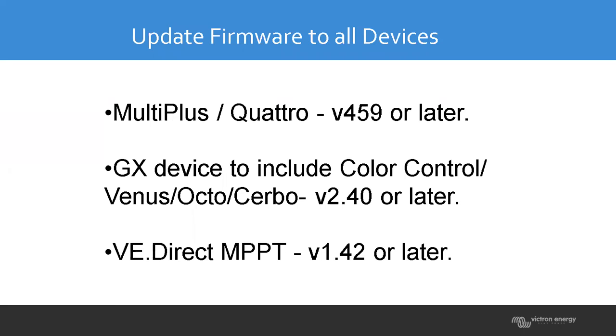We'll need to update the firmware to at least these firmware revisions. The Multi-Plus is 459 or later. The GX device, and that could be a Color Control or CCGX, a Venus, Octo, or the new Cerbo, you'd need at least the 2.4 version or later. You can do it with earlier versions, but there's some magic that really happened when the folks at Victron came out with this 2.4, and we'll discuss that later. You'll need version 1.42 or later for your MPPTs.